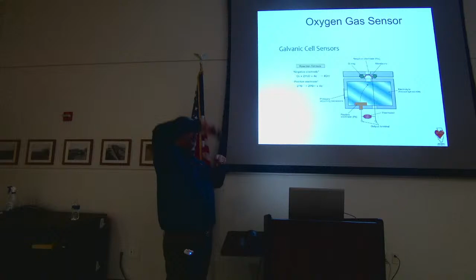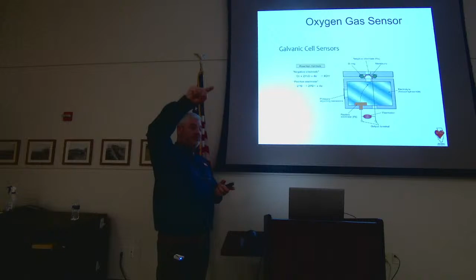We do have to calibrate it. Why? I'll go more into depth, but if I do a fresh air calibration with a fuel cell, I know what 20.9 output looks like electrically. If I challenge it with a gas, I then know what that output will be as well. I draw a linear line between good and bad gas. If in my equation the only thing that changes is this electrolyte, as it decreases I will have what's called drift, and that drift is inaccuracy. So we want to make sure these things are accurate.